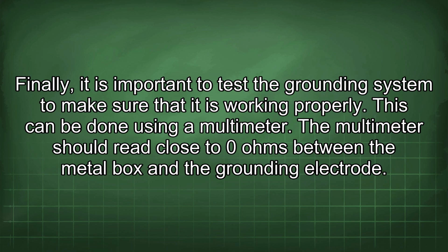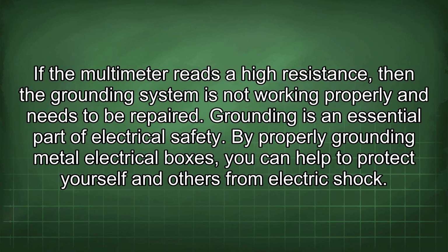Finally, it is important to test the grounding system to make sure that it is working properly. This can be done using a multimeter. The multimeter should read close to 0 ohms between the metal box and the grounding electrode. If the multimeter reads a high resistance, then the grounding system is not working properly and needs to be repaired.